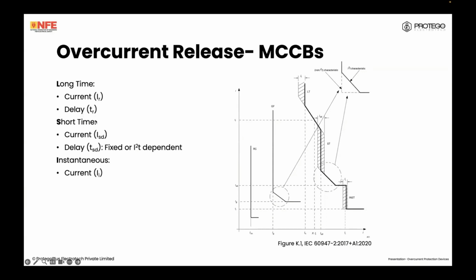Short time comes in when you have short circuits or earth faults of negligible impedance. You can say for short circuit currents between, say, maybe 6 to 8 times IN, there will be a delayed trip. This delayed trip can either be a fixed delay, so a certain amount of time, or depending on the current, it will trip at a certain value. So that is the let-through energy dependent characteristic.